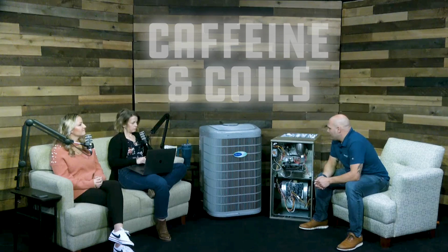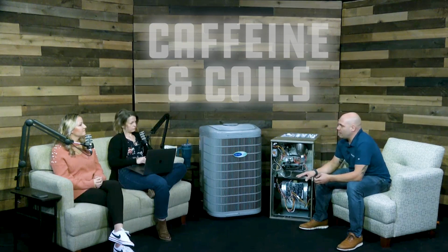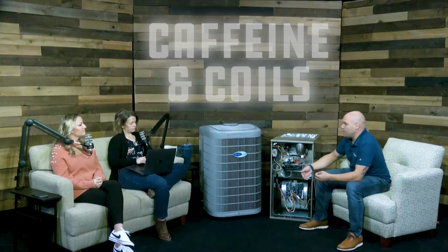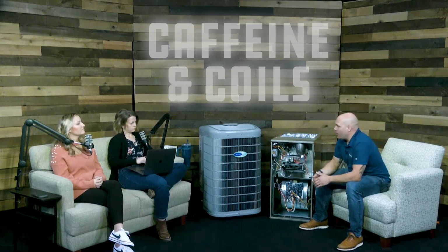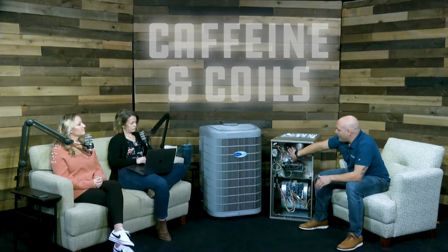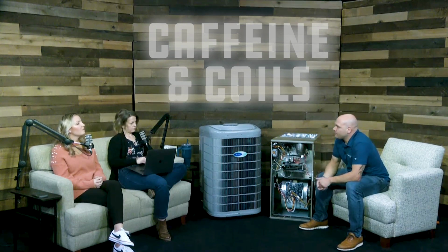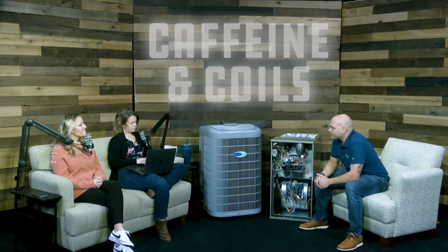So I would say it's a 50-50 chance if the part is actually bad. There's another 50% of the time where it could actually be something else, airflow or a bad part somewhere else. Okay. It's rare that the error code points directly to the problem. It just kind of gives you a general area to look, basically, right? Correct.